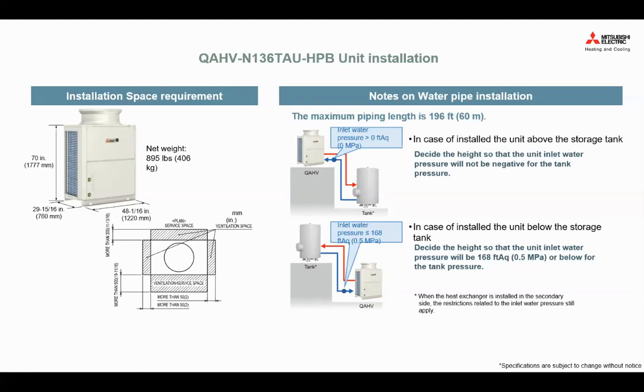However, one thing I always bring up is that the service space in the manual is always the minimum space. So I always recommend going a little bit higher, right? Not just because of installation, you also have to think about future service and inspection, and also cleaning the coil, right? You really have to think about whether you can reach it. Is 50 millimeters really big enough for someone to reach in and clean the unit properly? The answer is yes, but you really have to think about the people, right? I imagine the coldest night and someone is carrying a heavy bag and trying to service the unit. So think about the installer as well.